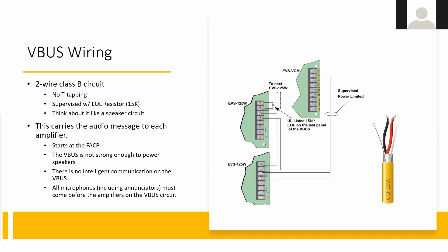On a recent job, we had an issue where one wire carried the VBUS going from the panel to a microphone, and then we also went from the panel to other amplifiers. To avoid pulling extra wire, we used the VBUS out from the microphone at the annunciator, pulled it to the VBUS in of the fire alarm control panel, and then went from the VBUS out on that panel to all the amplifiers. It still hit both microphones — the one at the enunciator and the one at the panel — and then went to the amplifiers. By keeping microphones first and amplifiers last, it worked correctly.